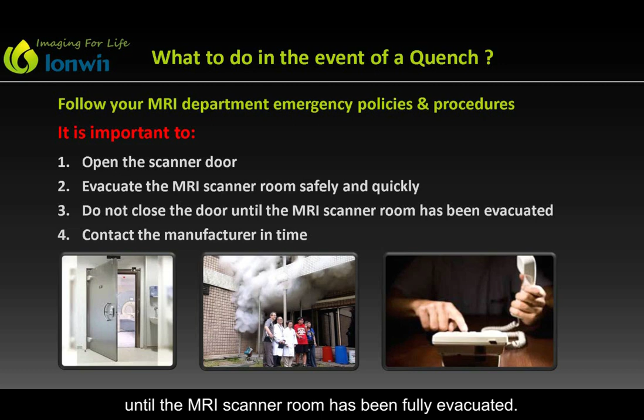In the event of a quench, it is important to do the following. Open the scanner door, evacuate the MRI scanner room as quickly as possible. Do not close the scanner room door until the MRI scanner room has been fully evacuated. Then contact the manufacturer in time.